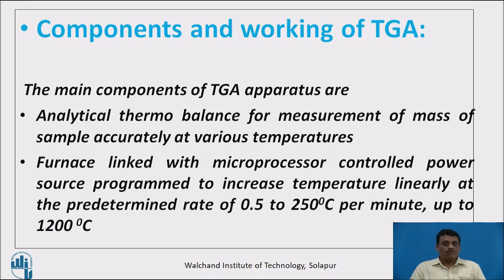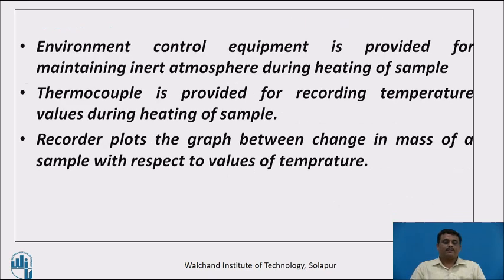The main components of a TGA apparatus are: an analytical thermobalance for accurately measuring the mass of the sample at various temperatures; a furnace linked with a microprocessor-controlled power source programmed to increase temperature linearly at a predetermined rate of 0.5 to 250 degrees centigrade per minute, up to 1200 degrees centigrade; environment control equipment for maintaining an inert atmosphere; a thermocouple for recording temperature values; and a recorder that plots the graph between change in mass and temperature.